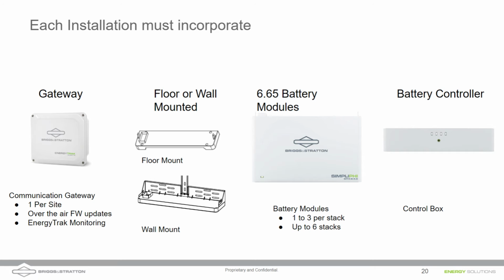The components that you need to do this battery, so this battery can be wall mounted or floor mounted. The modules themselves are coming in at a very strong price point, 6.65 kilowatt hour modules, and a controller box to go on the top. So each stack will consist of a floor mount or a wall mount, battery modules, and then a controller box. And the gateway itself will be used for firmware updates and individual monitoring of battery modules.